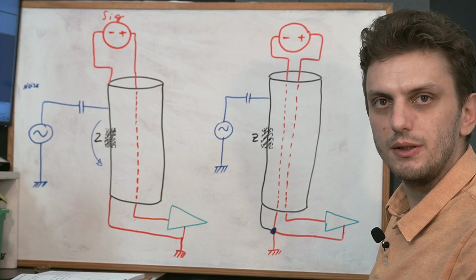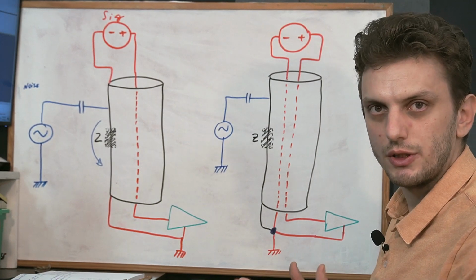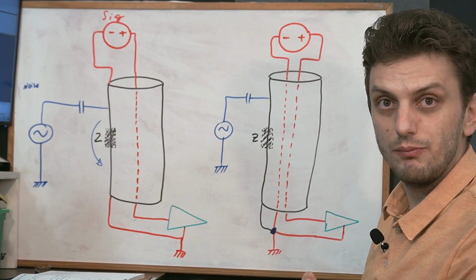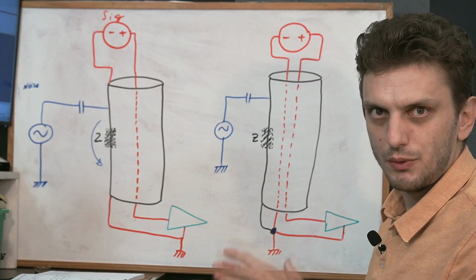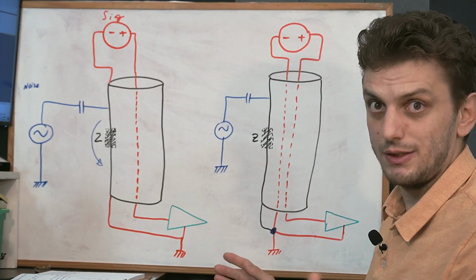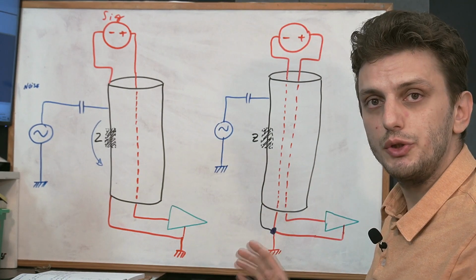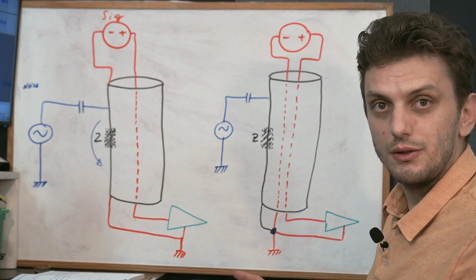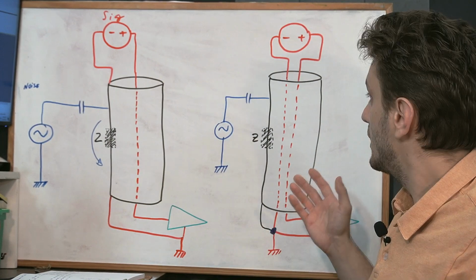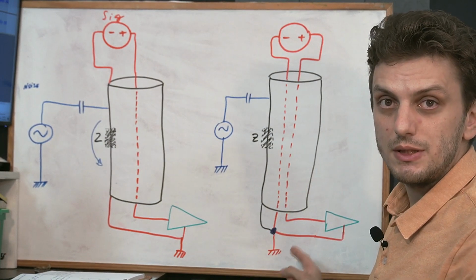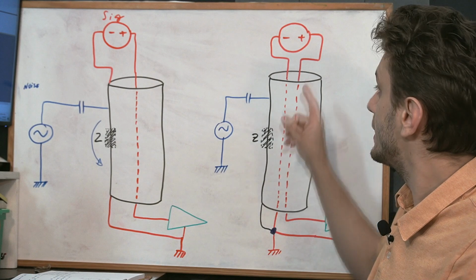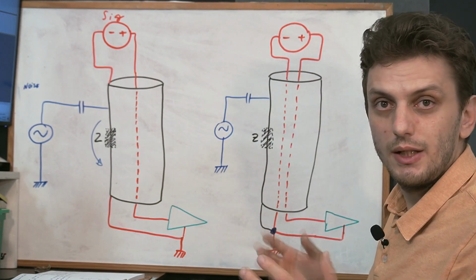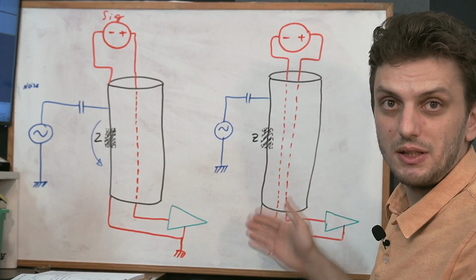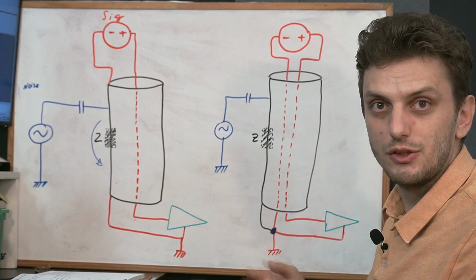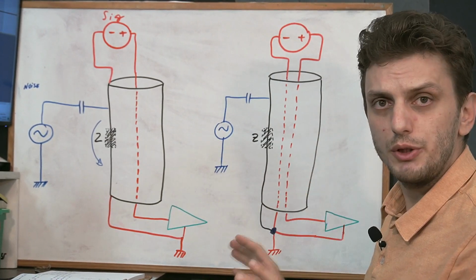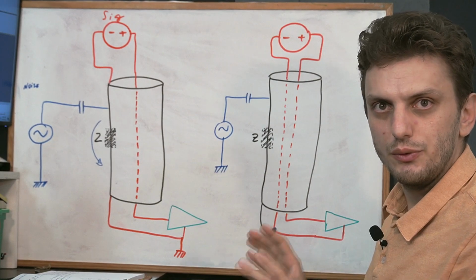Now it's worth mentioning that if you want to use a split ground concept, all the grounds need to be, first of all, interconnected - just because you call it ground doesn't mean it is ground. Secondly, you should use a single interconnection, so as not to create loops, because one thing you could do is connect the ground on the bottom side but also on the top side. Then this extra ground line is basically short-circuited by the external shield, so it's not doing anything. Point being, this will only work if you use it right.